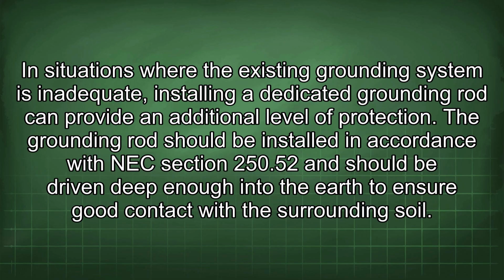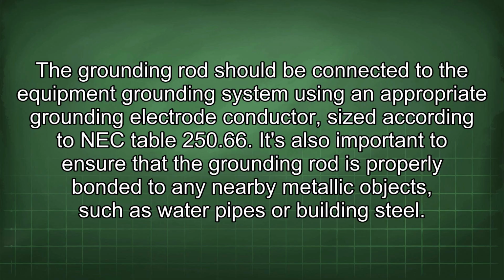In situations where the existing grounding system is inadequate, installing a dedicated grounding rod can provide an additional level of protection. The grounding rod should be installed in accordance with NEC section 250.52 and should be driven deep enough into the earth to ensure good contact with the surrounding soil. The grounding rod should be connected to the equipment grounding system using an appropriate grounding electrode conductor, sized according to NEC Table 250.66. It's also important to ensure that the grounding rod is properly bonded to any nearby metallic objects such as water pipes or building steel.